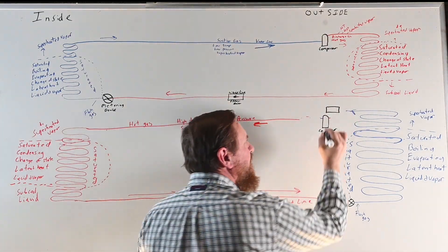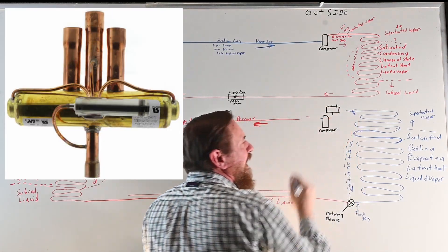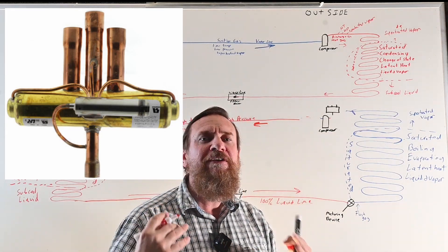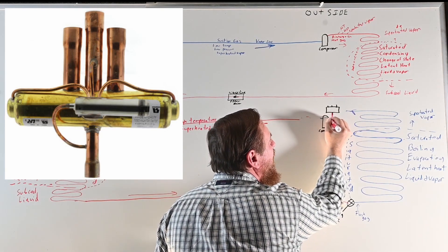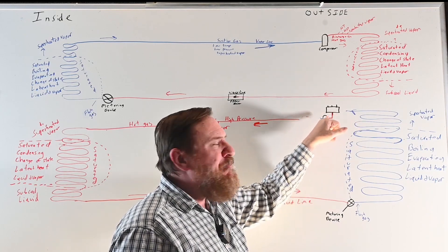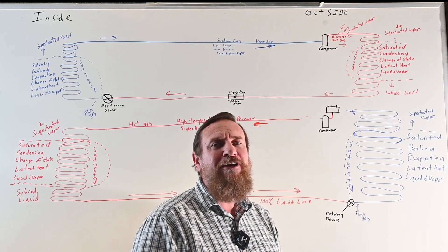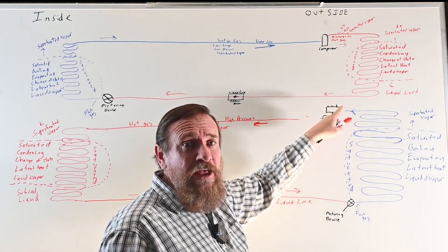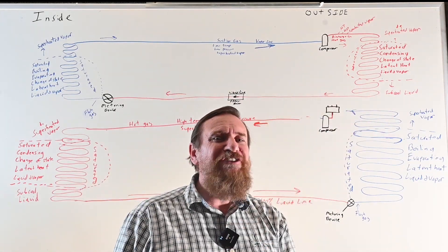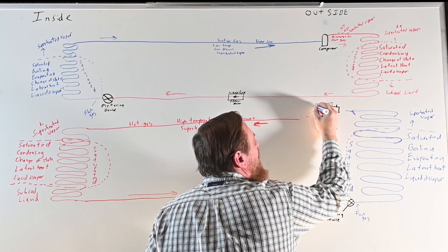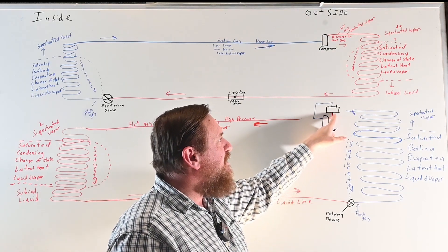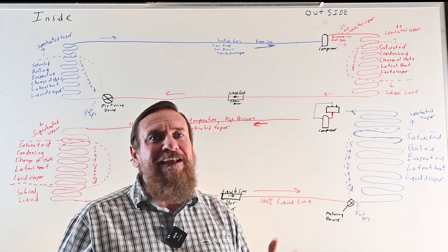This reversing valve has three pipes on one side and one pipe on the opposite side. The pipe that has only one pipe by itself is always the discharge gas — high temperature, high pressure, superheated vapor, always. If you look at any reversing valve and there's one pipe by itself, it goes straight to the compressor discharge. On the other side, the pipe of three — the one in the very center — is always going to be suction, what we call true suction. So the discharge line always goes to the one by itself, and the center pipe always goes back to the compressor suction. That's half the battle of the reversing valve.